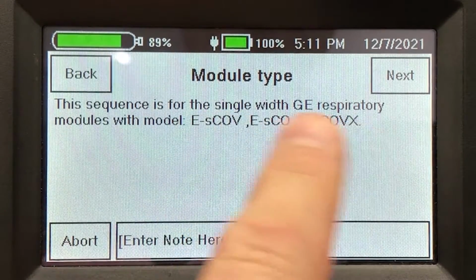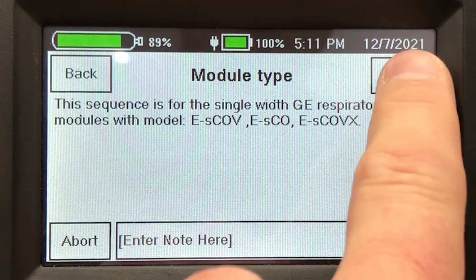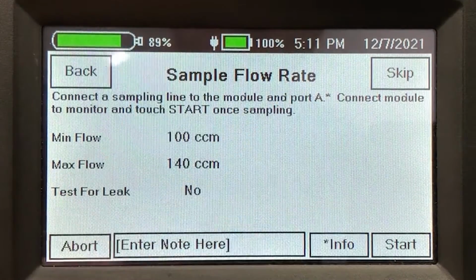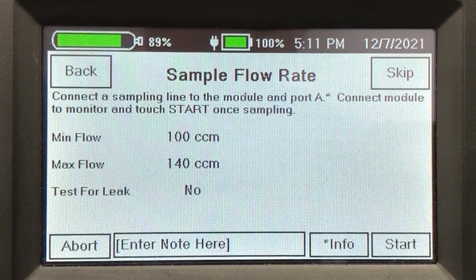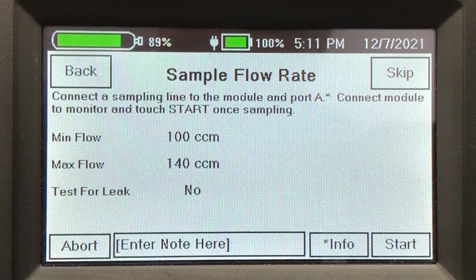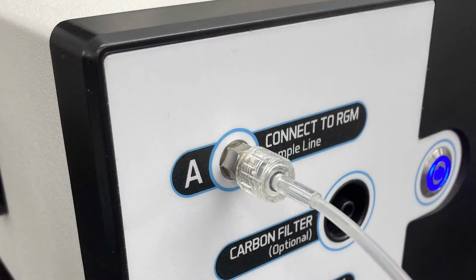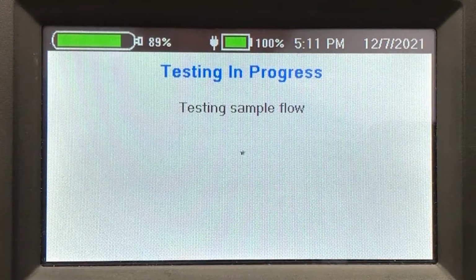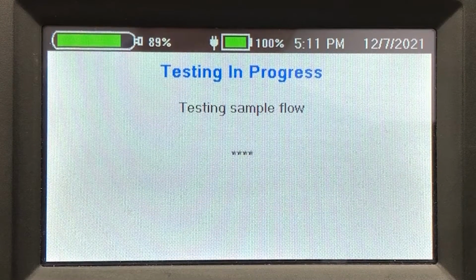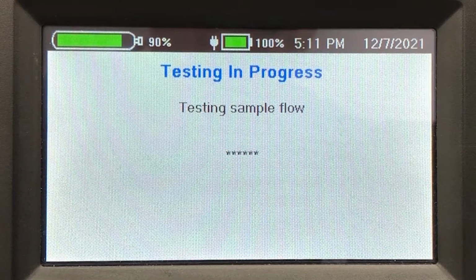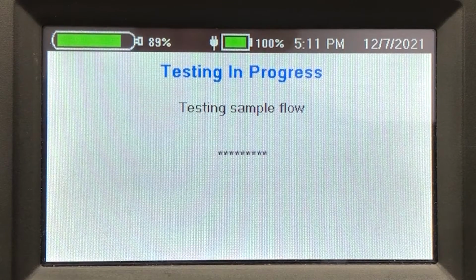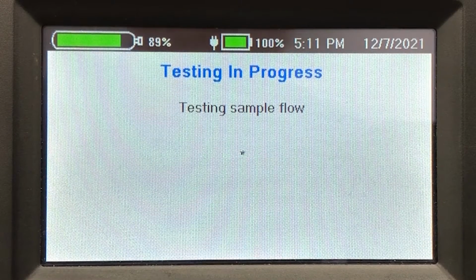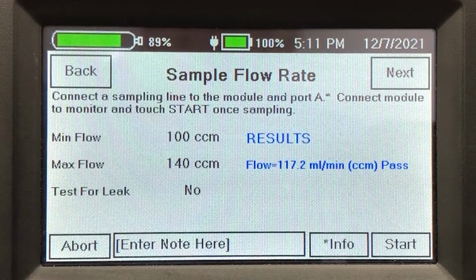You'll see here that this applies to actually 3 different modules. And the very first test is the sample flow rate. So we start by connecting the sample line between the water trap on the module and port A of the SmartTank. Then we press start. The SmartTank will measure the sample flow rate and compare it to pass-fail criteria. If the flow rate doesn't fall within the pass-fail criteria and we get a failing result, then when we hit next, it would walk us through the routine required to calibrate the sample flow rate. But in this case, because it passed, when we hit next, it'll just take us to the next test.